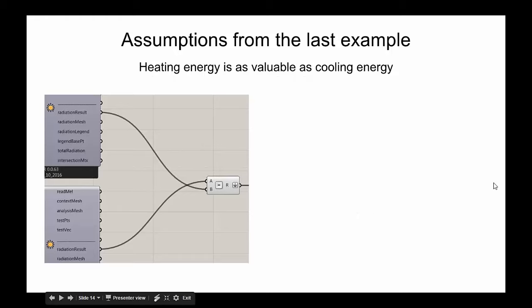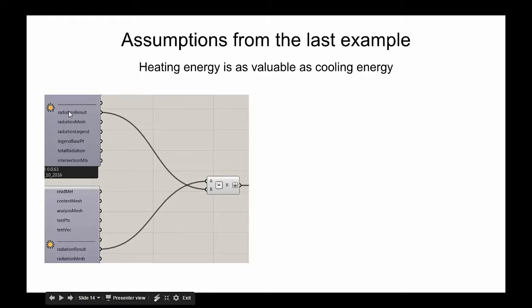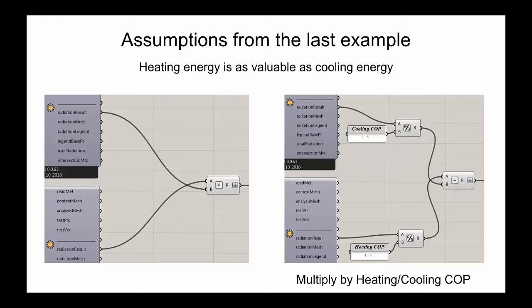Another assumption from the last example was that we simply subtracted bad radiation from good radiation — implying that heating energy is as valuable as cooling energy. While this is roughly true when you trace back to fossil fuel consumption, your specific building might be very different. For instance, if you're cooling with lake-source cooling and have a lot of free cooling, you could divide by the coefficient of performance of your heat pump to weight these two factors differently.